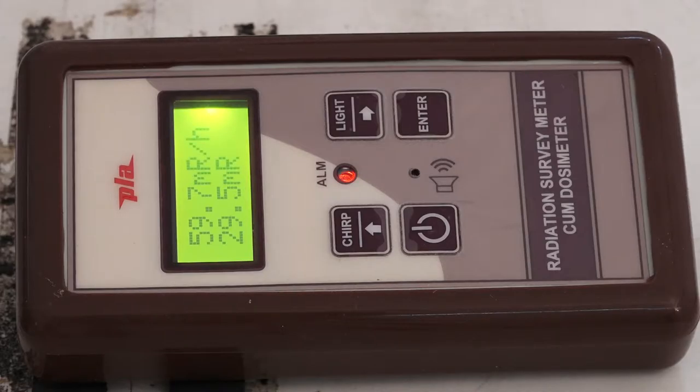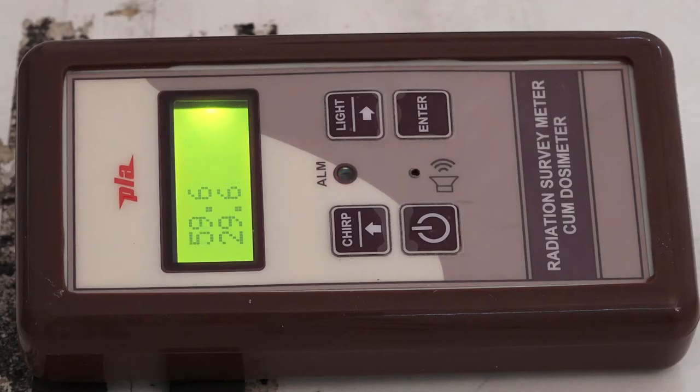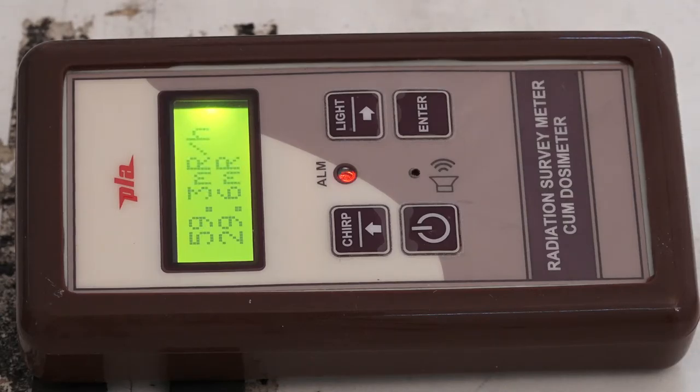If there is another source — say iridium-192 or cobalt-60 — the half value layer of lead will be different; it is not the same for all gamma energies. It is a function of the gamma energy. We will now apply the half value layer for the cesium-137 source and take the reading.